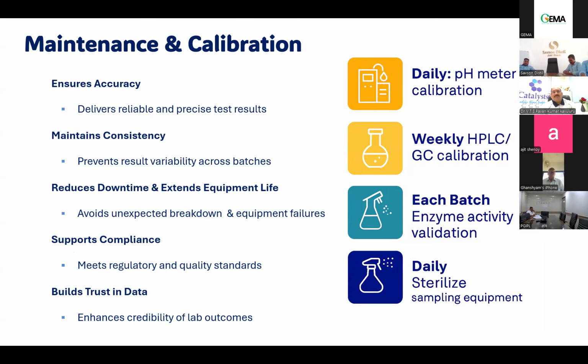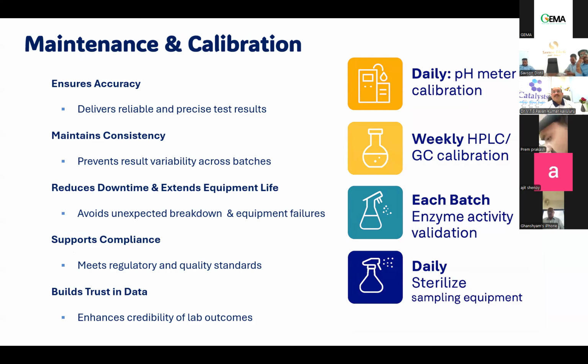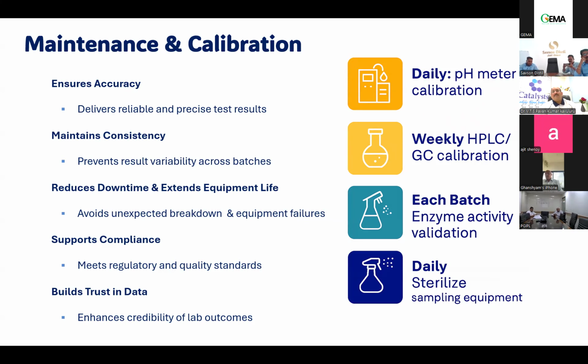One other important aspect which we have to ensure is maintenance and calibration of our equipment. It is very important. Many times we face the challenge of erroneous results, and this is mainly because of maintenance and calibration activities. If calibration and maintenance were not done for the equipment, even for the smallest equipment like a pH meter or the weighing balance, if these were not calibrated as per the standard guidelines, whatever analysis we do may have erroneous results. So we have to ensure the equipment is maintained and calibrated at the right time for better accuracy, to maintain consistent results, to reduce downtime, and to extend the equipment's life. Maintaining and calibrating it is very important.